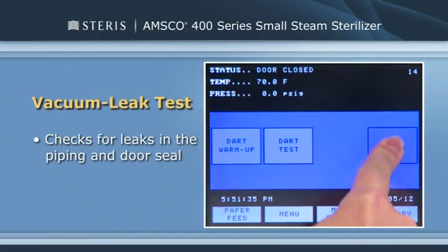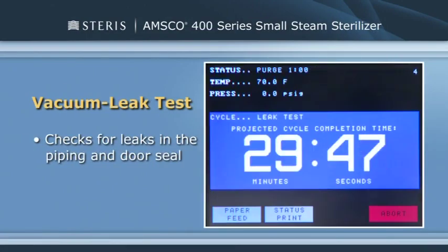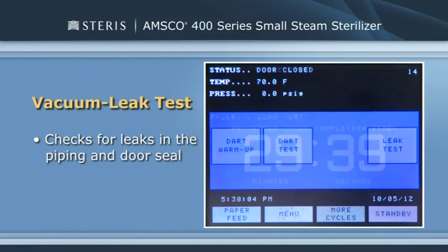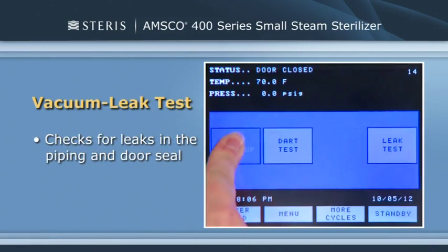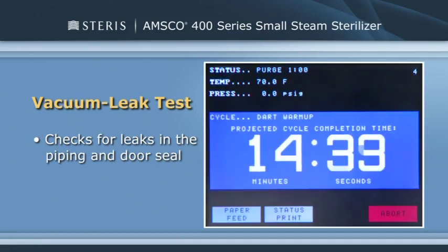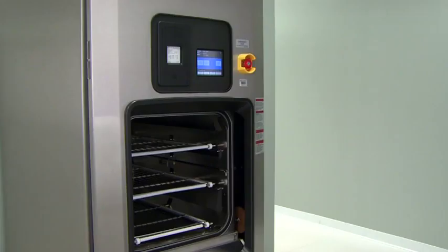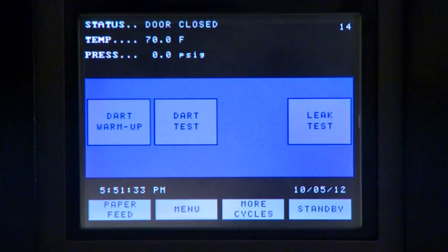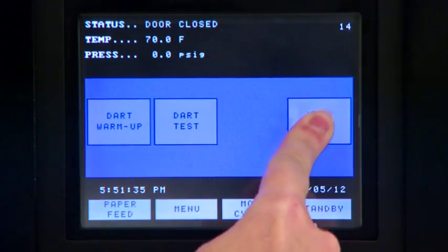The vacuum leak test should be performed at least once a week. It automatically checks for leaks in the piping and door seal. To ensure valid test results, always run a warm-up cycle before performing this test. When the warm-up cycle is finished, initiate the vacuum leak test. The sterilizer chamber must be empty while running this test cycle. From the Test Cycles menu, press the Leak Test button.